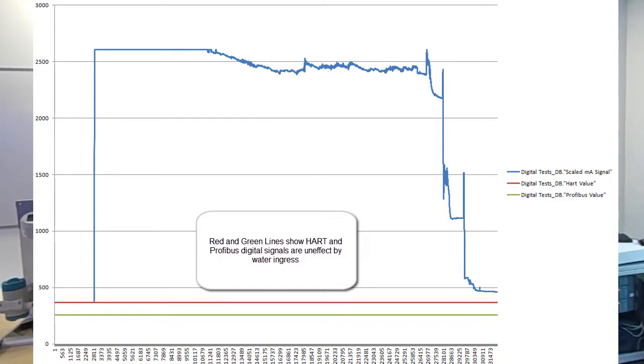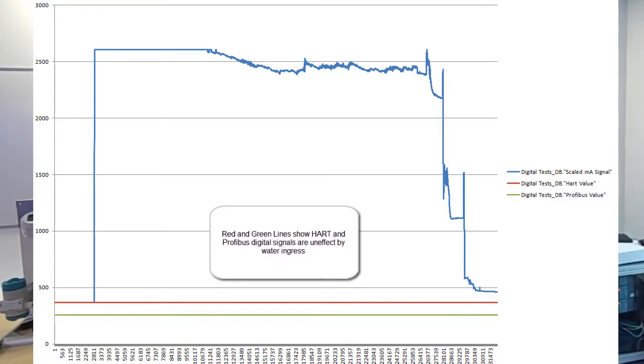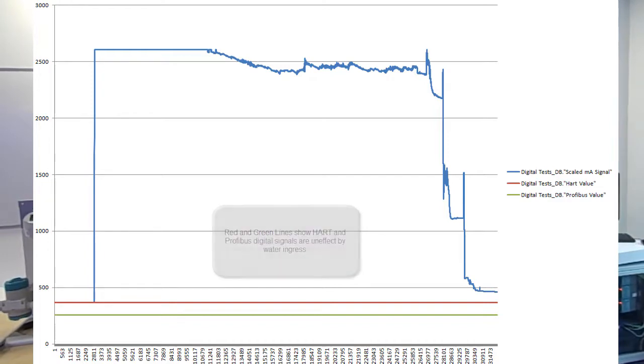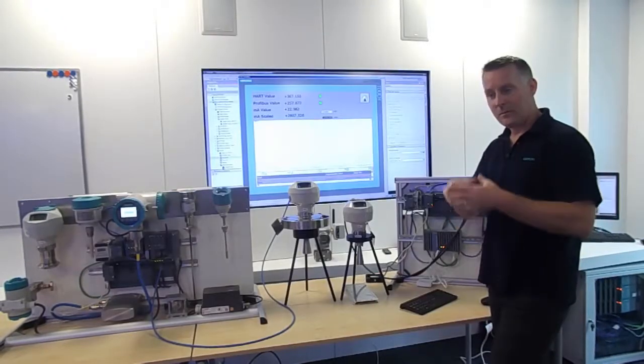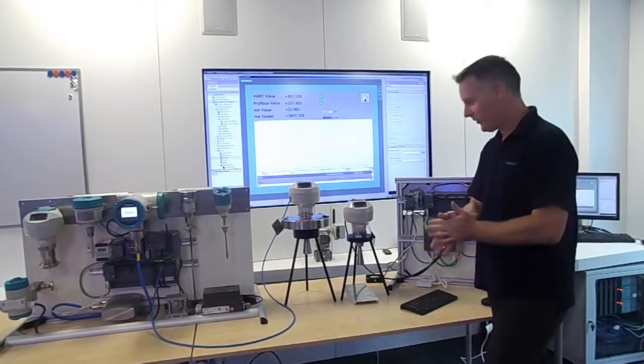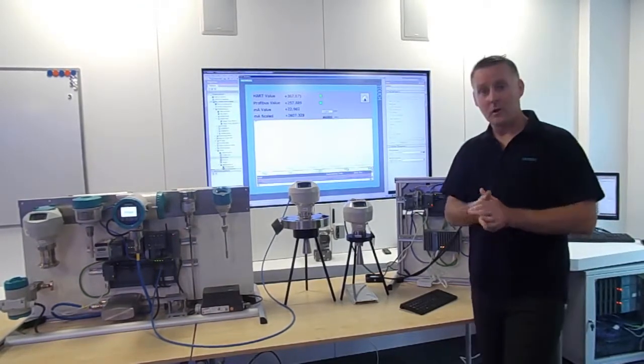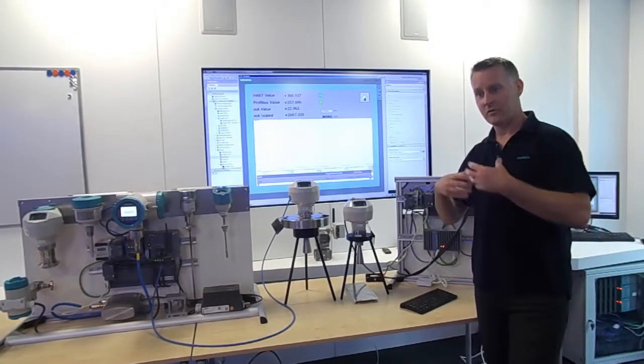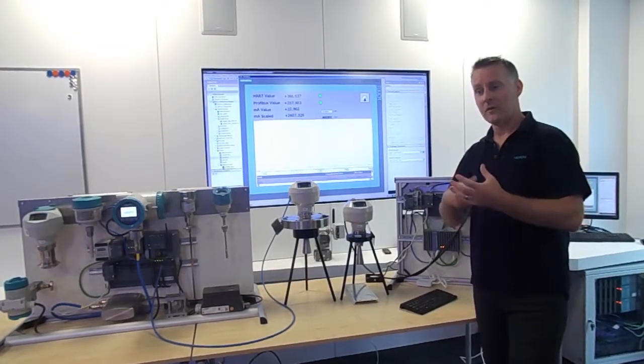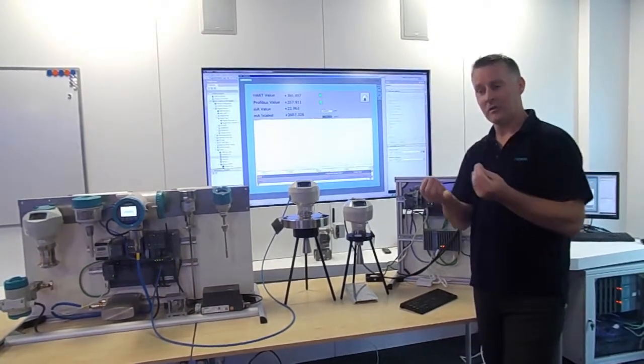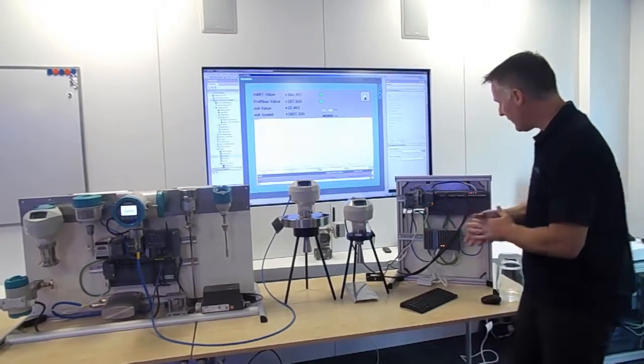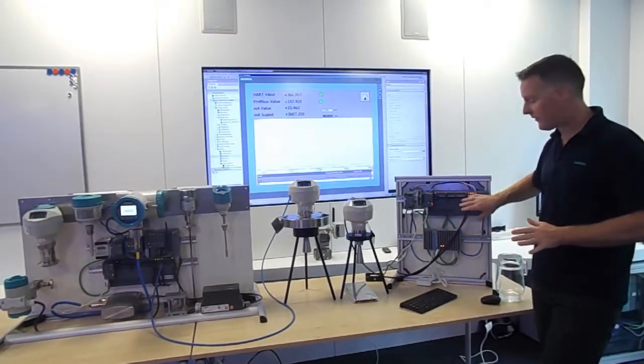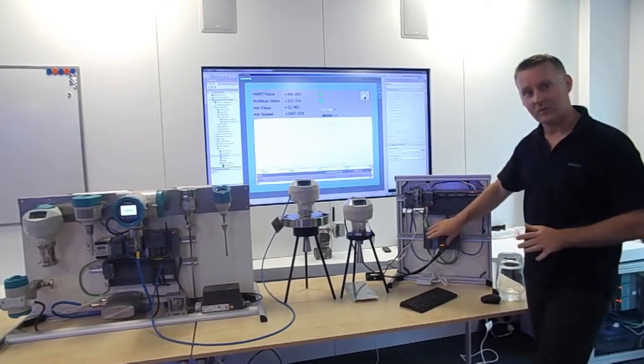But what I can see from the results is my digital values are steady. They are not being affected by the water ingress. Now with Profibus that would probably be okay. But after a certain amount of time on a Profibus network using low cost split connects we would start to see that corrosion on the connections starting to cause network issues.